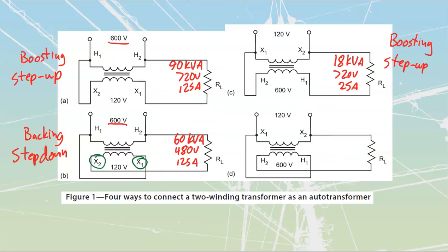Let's just put this one up onto our main one. Let's drop these values in that we have. 480 volts. 25 amps, 12 kVA that we have for this one. And then the last thing that we need to talk about is what is its setup.